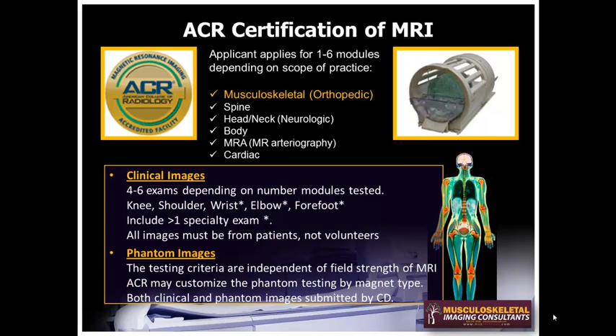The ACR requires the scanning of Phantom images. In my opinion, MRI imaging is like great music. It all depends on being in tune. You can have a great song to sing, but if the guitar is out of tune, it just doesn't sound very good. On the right is a cylindrical shaped Phantom that's placed in the scanner, and Phantom images are obtained of this Phantom. Scanning a test Phantom evaluates the technical performance of the MRI scanner.